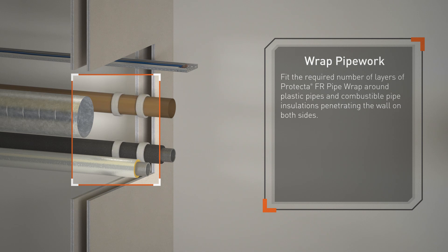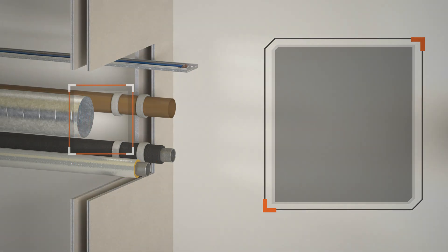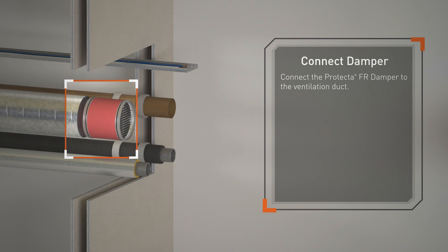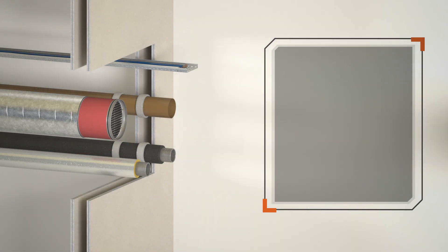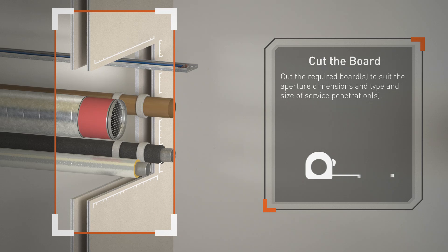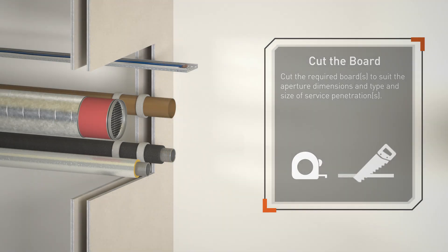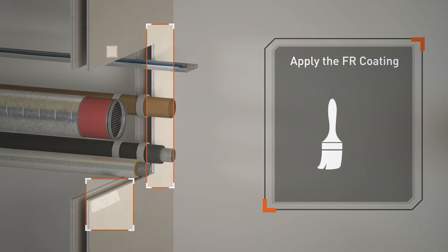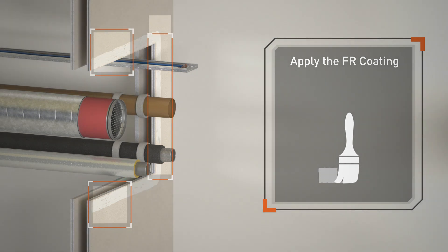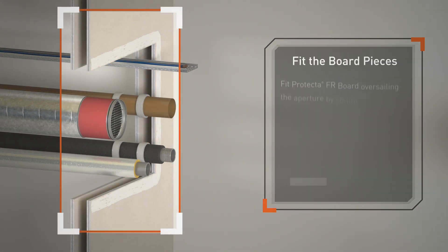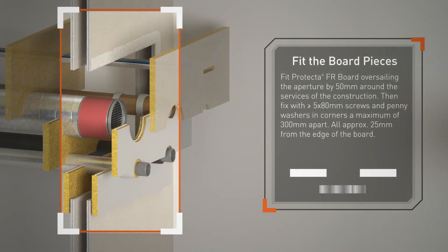Connect the Protecta FR Damper to the ventilation duct. Cut the required boards to suit the aperture dimensions and type and size of service penetrations. Apply the FR coating. Fit Protecta FR Board, oversailing the aperture by 50 millimeters around the services of the construction.